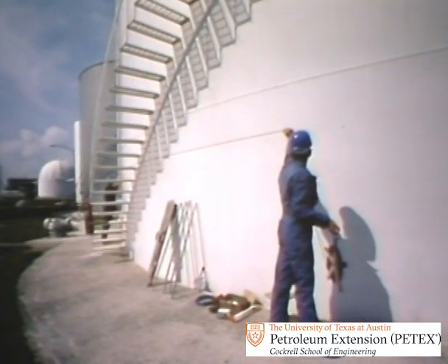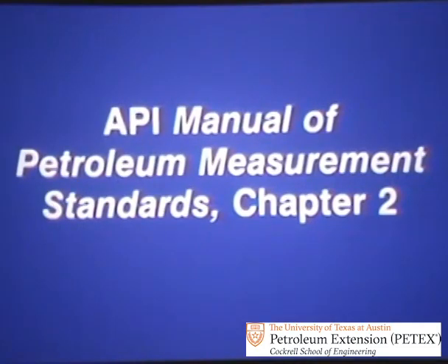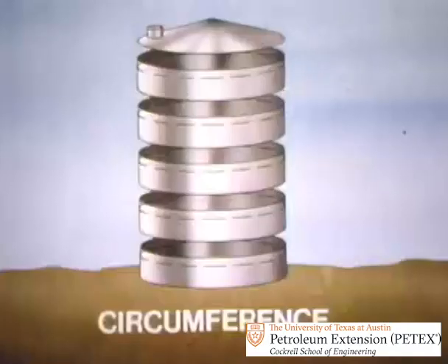So what you're about to see is one acceptable method of strapping a tank. It's based on the API Manual of Petroleum Measurement Standards, Chapter 2. This manual contains procedures that, if followed, give accurate tank measurements. Part of the procedure calls for the strapping crew to measure the circumference of each ring of the tank. So let's begin by watching a crew do this.